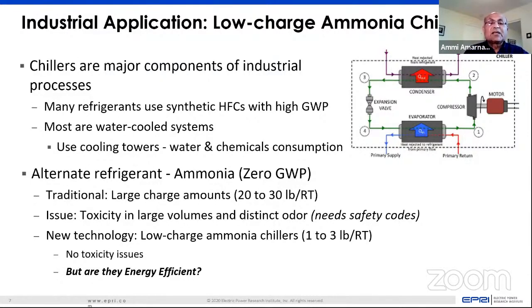There are safety codes. New technologies are coming into the marketplace that use ultra low charge ammonia, in the range of 1 to 3 pounds per ton of refrigeration. That's already more than an order of magnitude reduction in the amount of ammonia used.